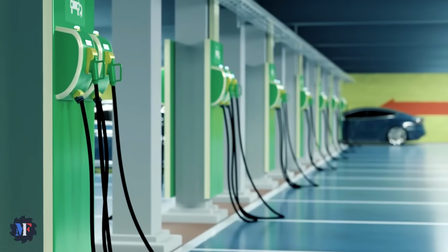With a charging station, you're up to code and it's 2 to 3 times faster than a reinforced outlet. You can program it and check the data through an app. It comes in 3.7 kilowatts and 7.4 kilowatts if you have single phase, or 11 kilowatts or 22 kilowatts if you have 3 phase. That's more suited for parking lots or rest areas.